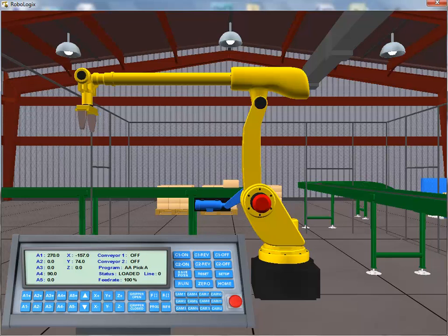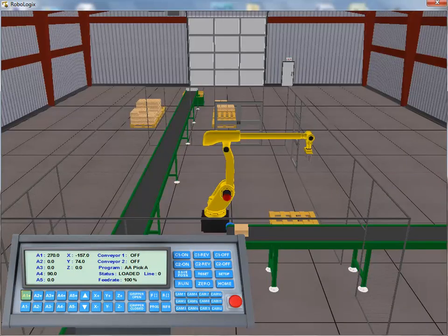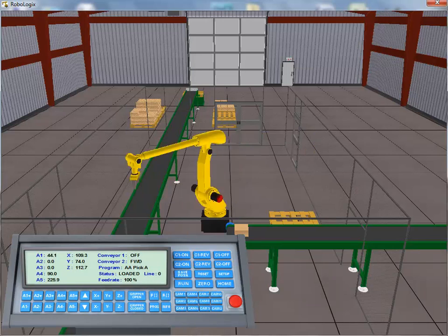After clicking on the Home Position to reset the arm, we click on Camera 11 again to have a better view of the next target location. Once again, we use the A1 button to jog the tool center point in an angular motion. This time, we want to position it directly over Conveyor 2. When we've arrived over Conveyor 2, we click on the Camera 12 button. This button gives us a bird's eye view looking down from the tool center point, and we can make fine adjustments using this camera angle. Once we've confirmed the tool center point is in the appropriate location, we click Save Position to add this third of four desired locations to our position register.